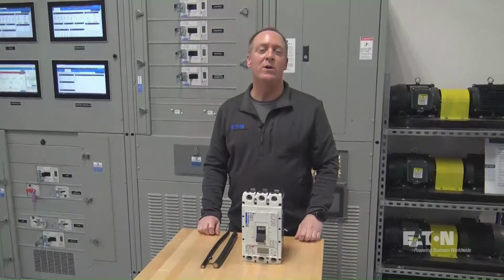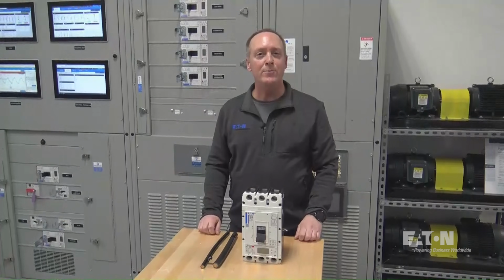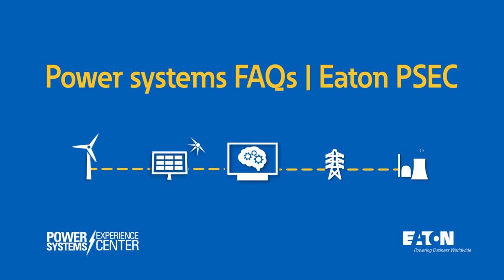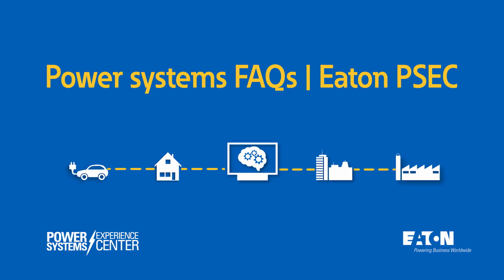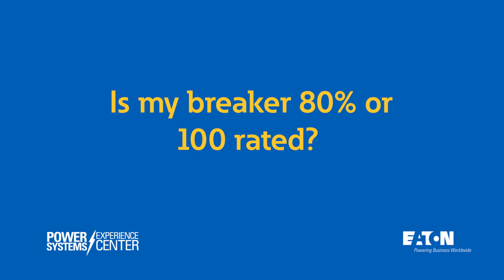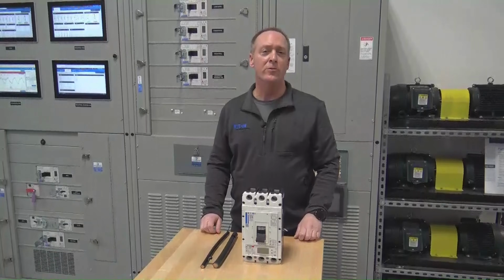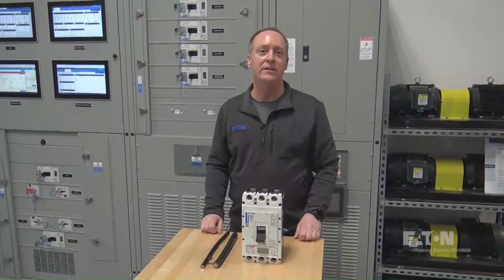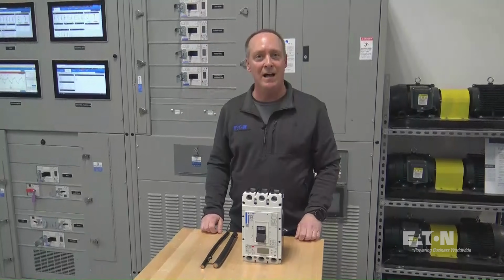One of the most common questions we get about molded case circuit breakers is, is my circuit breaker 80% rated or 100% rated? The truth is, all molded case circuit breakers are rated to carry their nameplate amperage continuously. The difference is how they're applied.